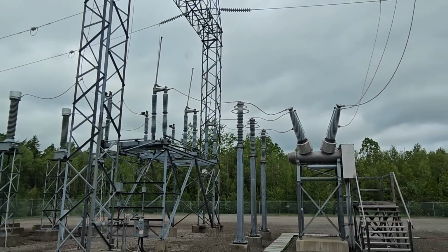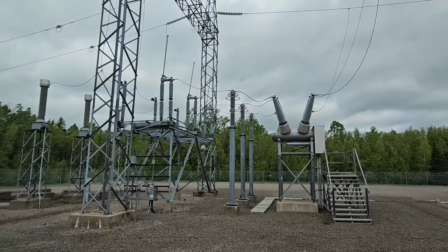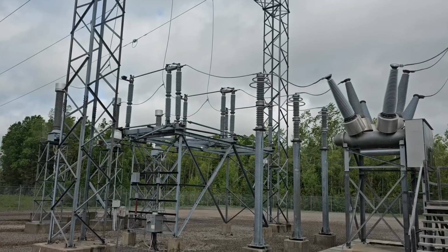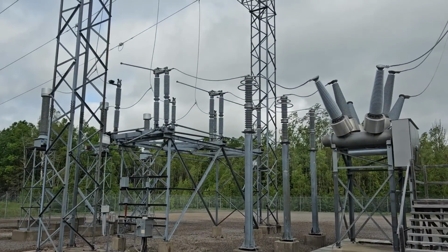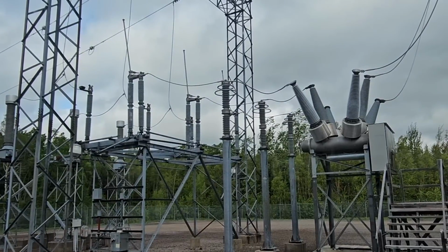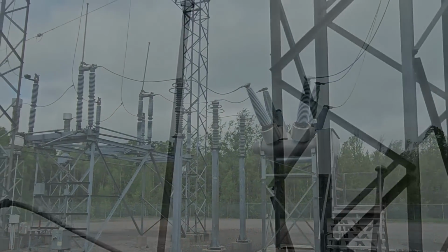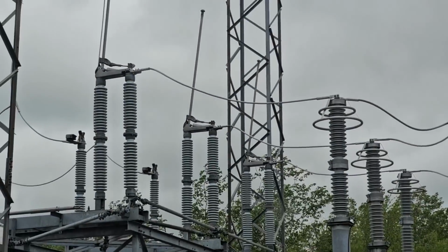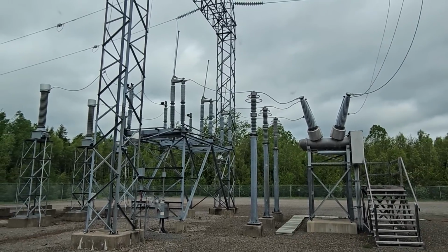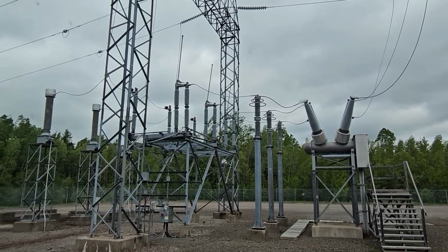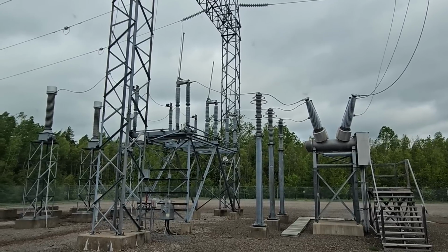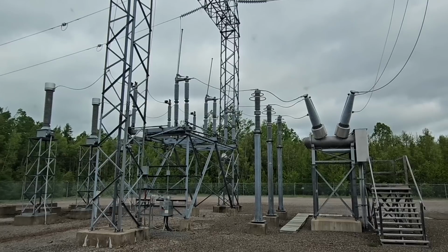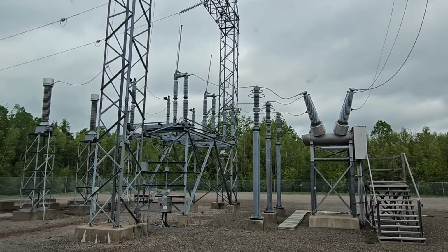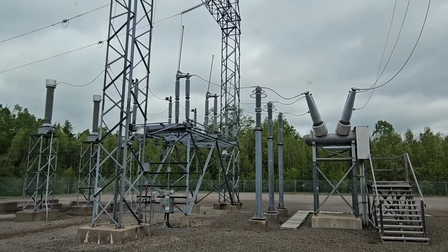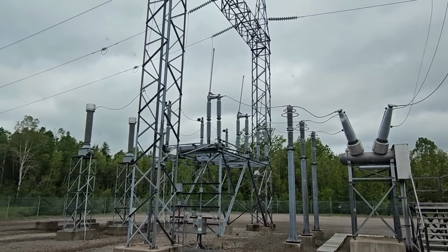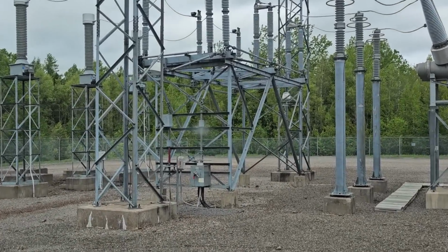So my steps here today, our power system operator opened that interrupter, and then they also remotely opened that disconnect switch. Let's zoom in just so you guys know exactly what I'm talking about. This disconnect switch right here, and that blade right there. So my steps, even though this can be done remotely, they can't just hit a button and open that breaker and then open that disconnect, because even though the computer confirms it was open, we do have to have somebody on site to check that that device actually did open, and then we stand clear and they remotely open that disconnect.